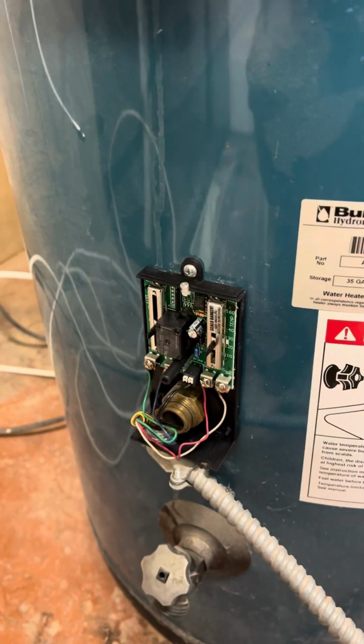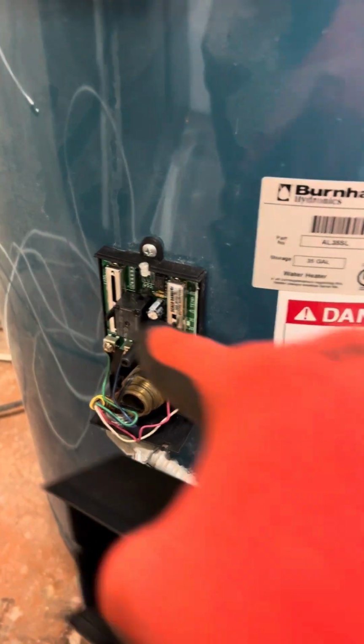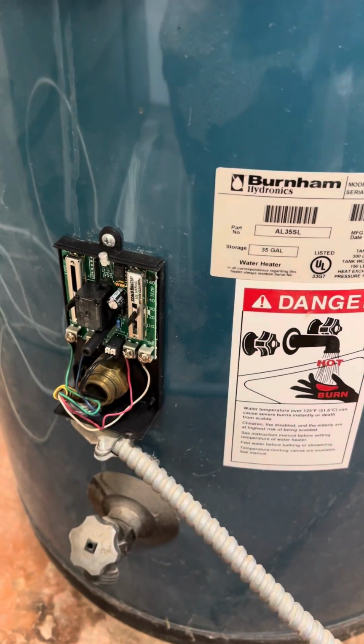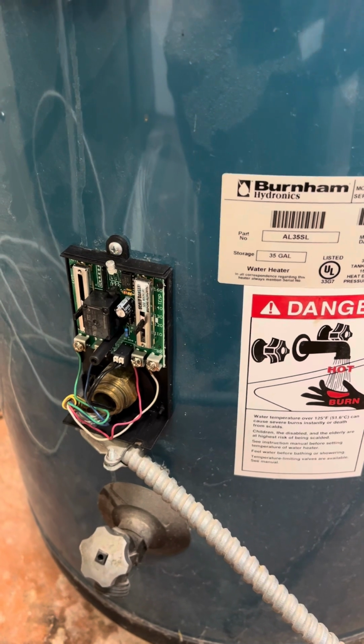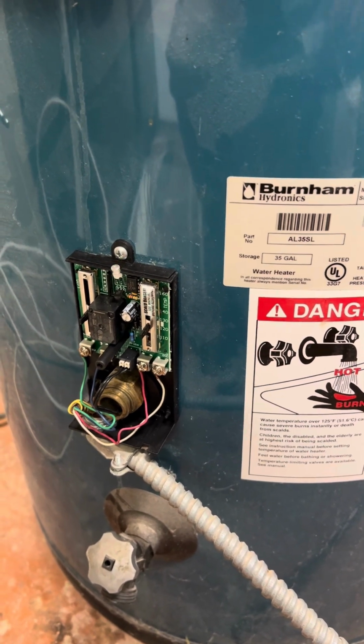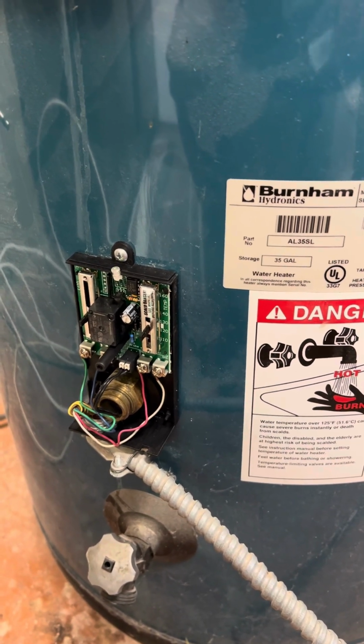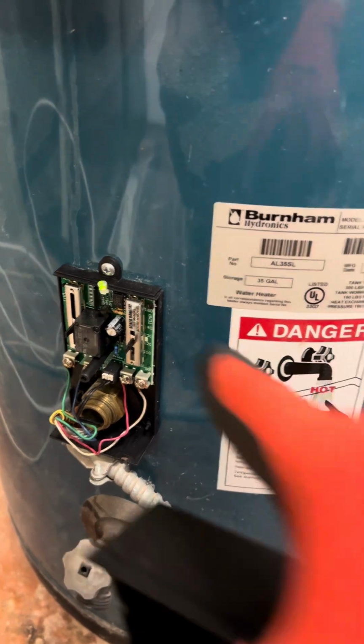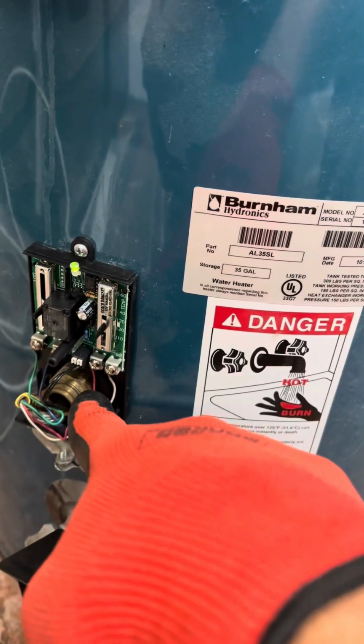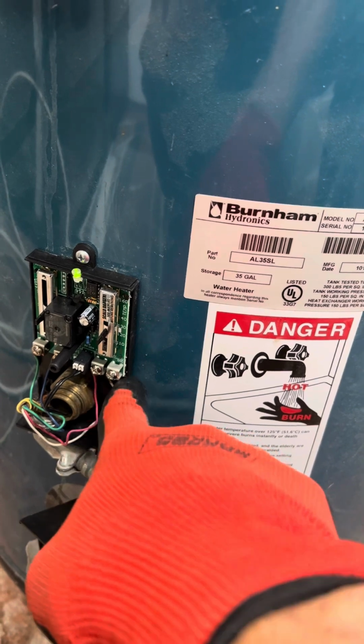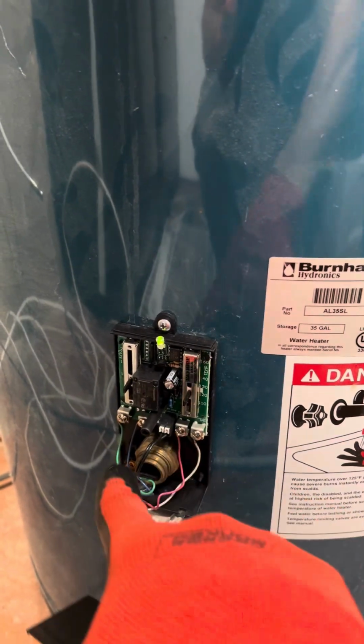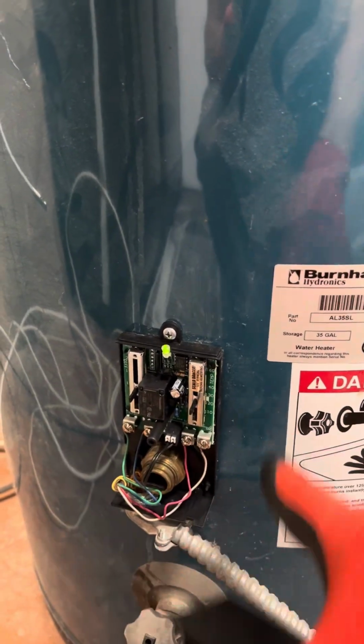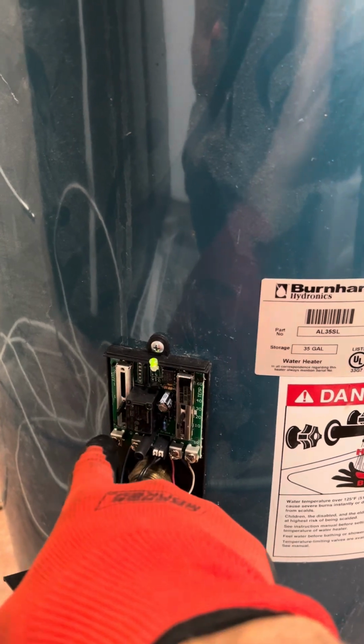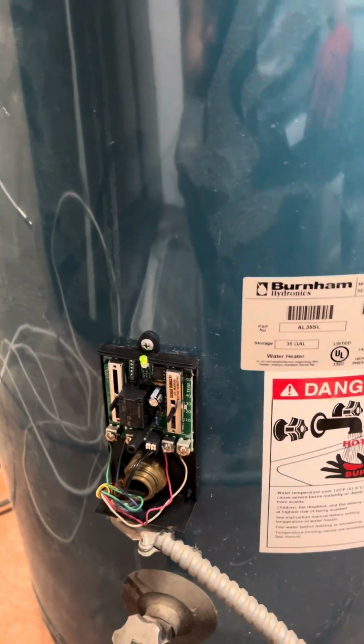So my problem wasn't the probe, because I had no red light, I had no lights over here at all. So it'll tell you if the probe is OL, open line, if it's broken for some reason. All right, then you just change out the probe. But mine was no lights at all, even though I had 24. So this 24, that's coming from the transformer right up there. As long as you got 24, this should be working. All right, and then this will be able to open and close with the temperature.